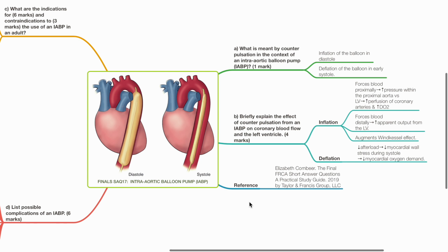Inflation of the balloon also forces blood distally, increasing apparent cardiac output from the left ventricle. Inflation of the balloon augments Windkessel effect. Deflation of the balloon reduces afterload, thus reducing myocardial wall stress during systole, and this reduces myocardial oxygen demand.